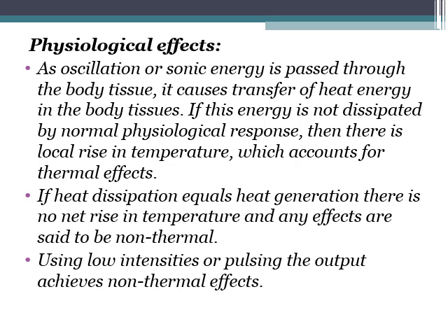And if the heat dissipation equals the heat generation, then there is no net rise in temperature. This effect is known as non-thermal. So through ultrasound we can produce thermal as well as non-thermal effects. If we want to produce more non-thermal effect, then we must use low intensity and pulsed output of ultrasound.